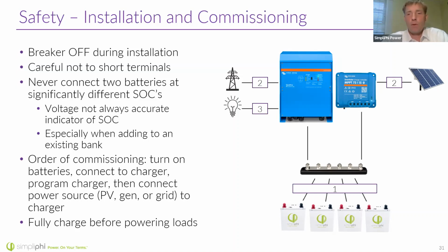It's also very important to never connect two batteries with different voltages. If the voltage on one battery differs by 1.5 volts compared to another, we don't want to hook those two up in parallel. A higher voltage battery could rapidly discharge into the lower voltage one, essentially creating a short circuit condition. If batteries have more than a 0.5 volt difference, we recommend never hooking them directly in parallel, since that difference can cause one battery to rapidly charge the other, damage the batteries, and void your warranty.